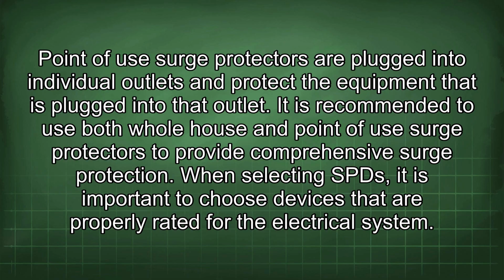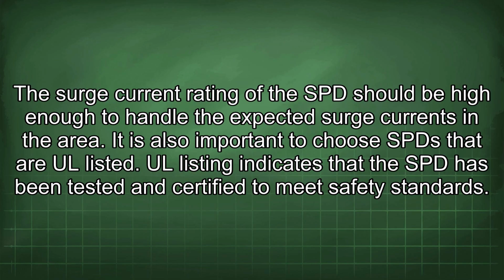When selecting SPDs, it is important to choose devices that are properly rated for the electrical system. The surge current rating of the SPD should be high enough to handle the expected surge currents in the area. It is also important to choose SPDs that are UL listed. UL listing indicates that the SPD has been tested and certified to meet safety standards.